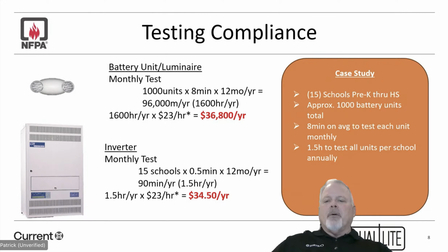This is just another example. If you use a battery unit luminaire, you do your monthly tests. In this particular case, we're talking about 1,000 units versus 1 inverter. So over that, having to test every month, 1,000 units based on the hourly wage, this could potentially cost the end user or customer over $36,000 annually versus the monthly test that we do and the yearly test that we do.